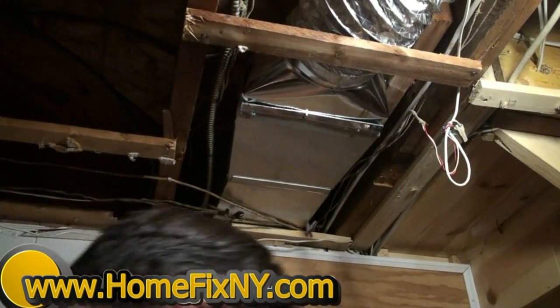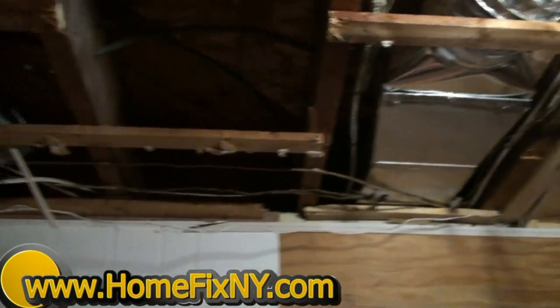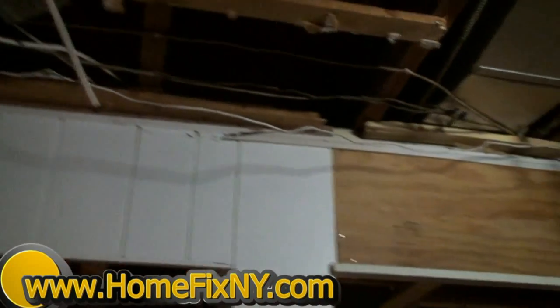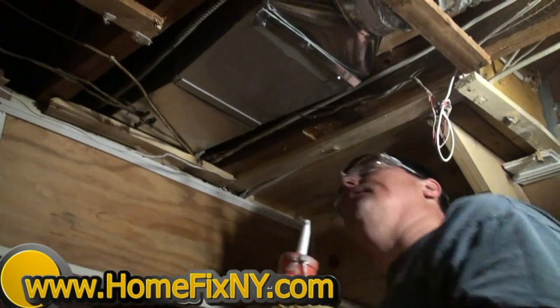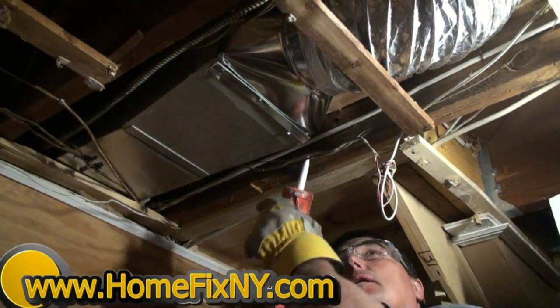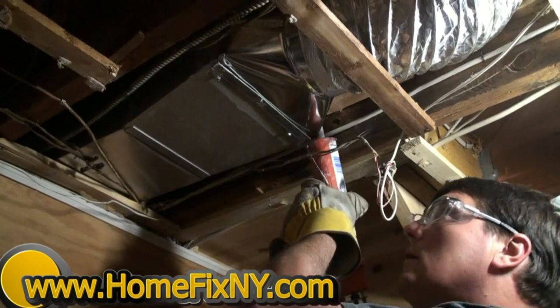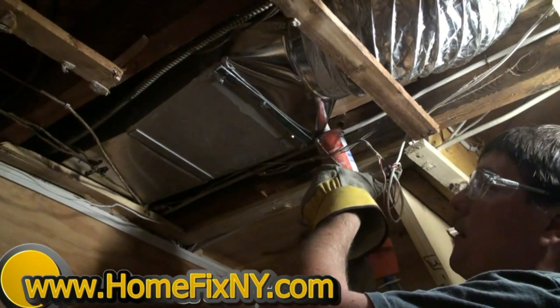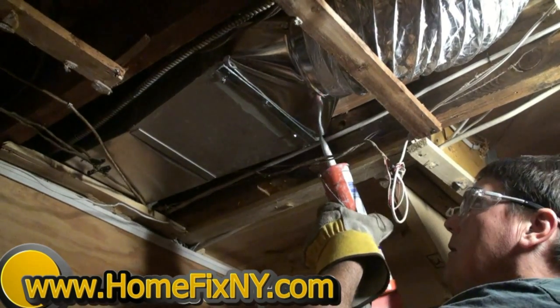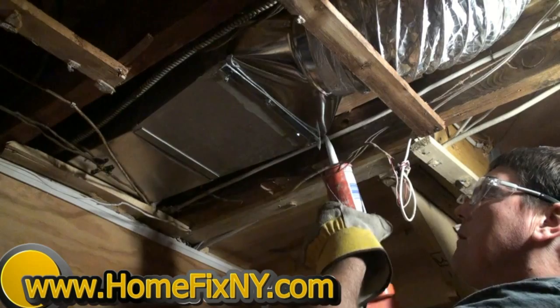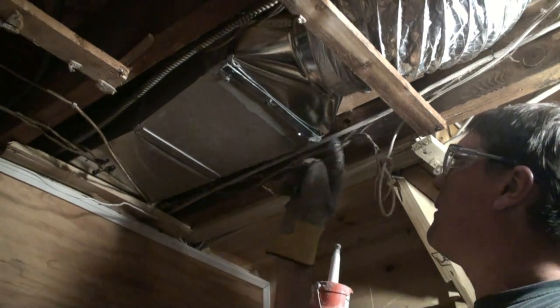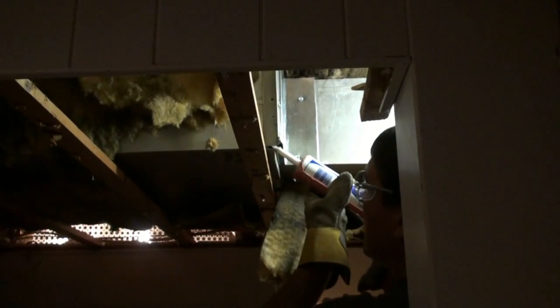And the next biggest issue was the register that was just pointed up toward the floor. What we wanted to do was cut that back all the way to the plenum. As much of the ductwork as we could remove, we wanted to remove because you don't want that conductive heat loss through extra vents or ductwork that you don't need. So we cut that all the way back to the plenum, the register that was pointing toward the floor, and we plated it up and we sealed it up good.